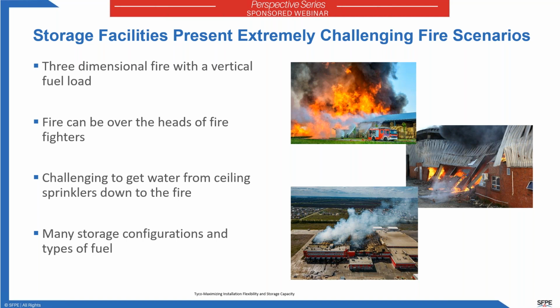So storage facilities, as I'm sure most of you on this call know, present extremely challenging fire scenarios. Those of you who are familiar with NFPA 13, the standard for designing and installing fire sprinkler systems, know that NFPA 13 essentially looks at two different types of applications. One I would call occupancy applications, and then warehouse applications or storage applications. Occupancy applications, as you know, give you your hazard classification, whether that occupancy is considered light hazard or ordinary hazard or extra hazard or potentially residential. And sprinklers that are used there are traditionally called controlled mode density area sprinklers, or CMDA, and those systems are designed using area density curves. You figure out what your occupancy is and your hazard, and then you can determine what your hydraulic requirement is based on the area density.